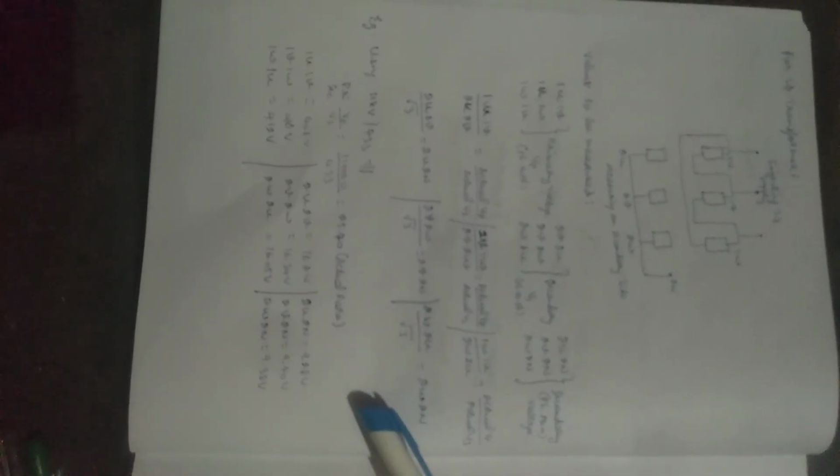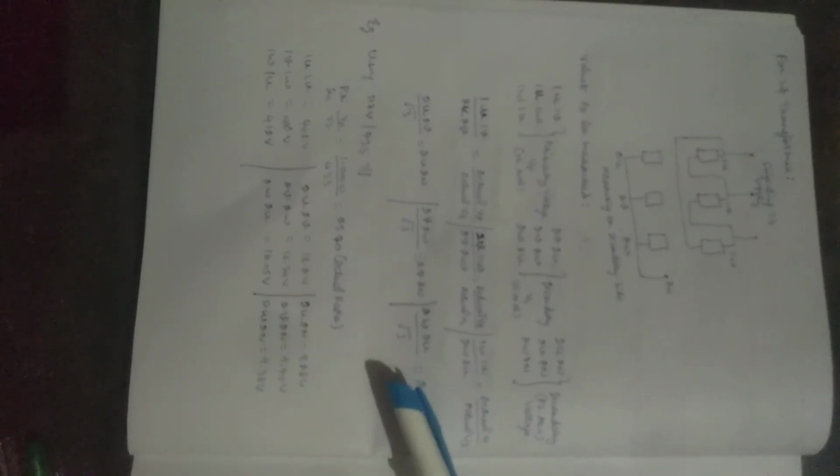After this, we need to measure all these values and compare them with the actual value, which is on your nameplate itself. The transformer ratio values are on the nameplate, and then you need to do the error calculation for it.